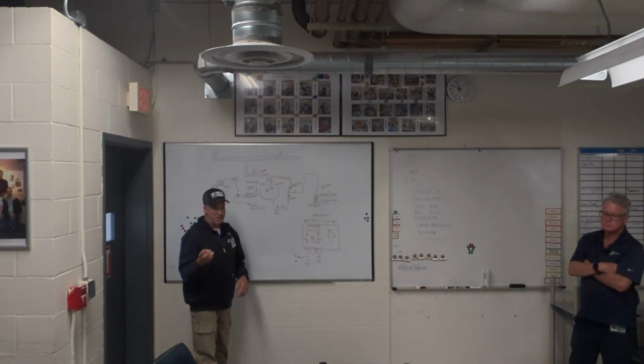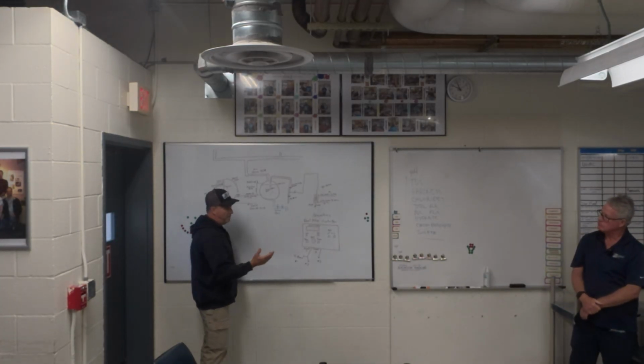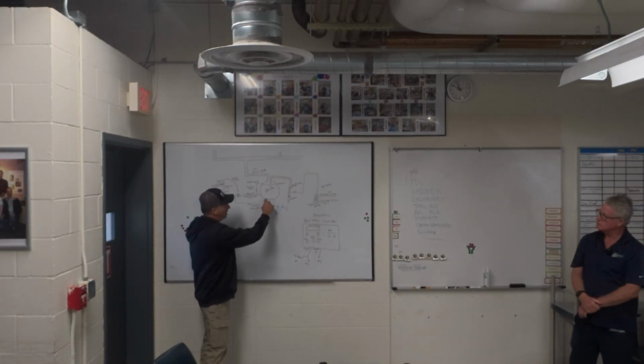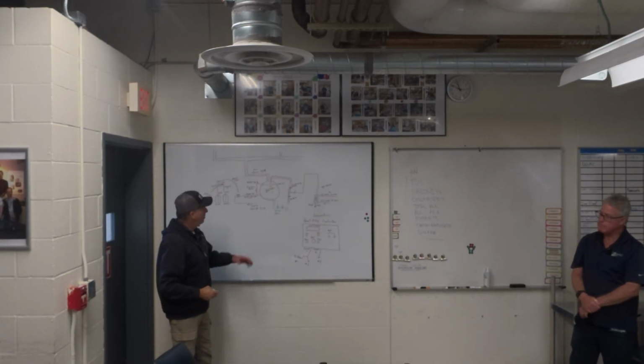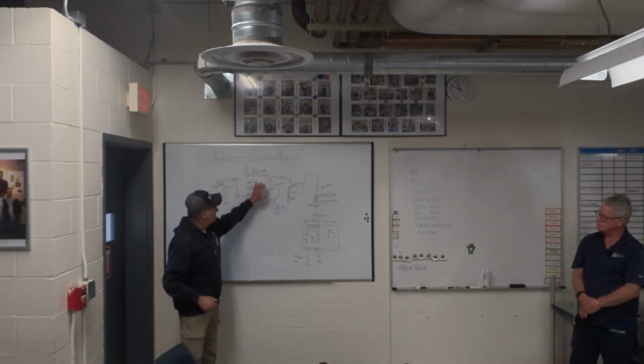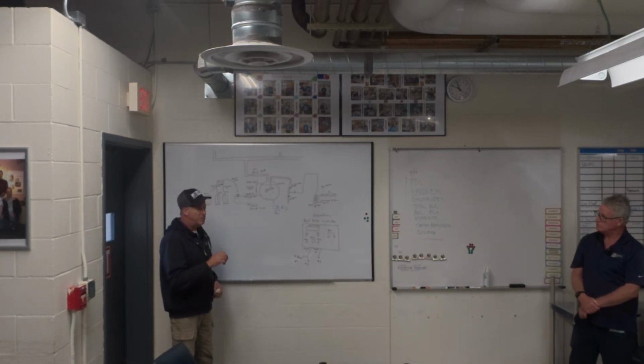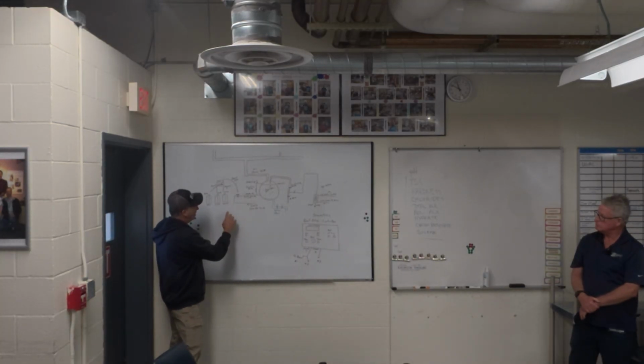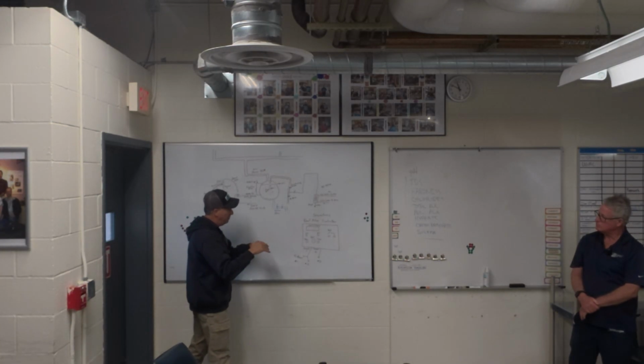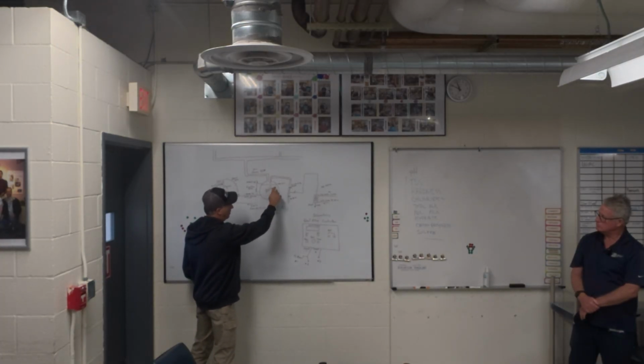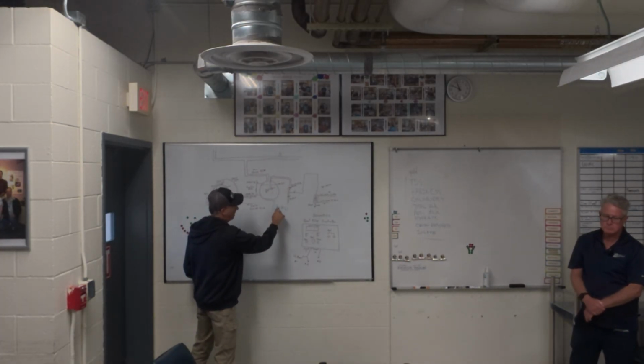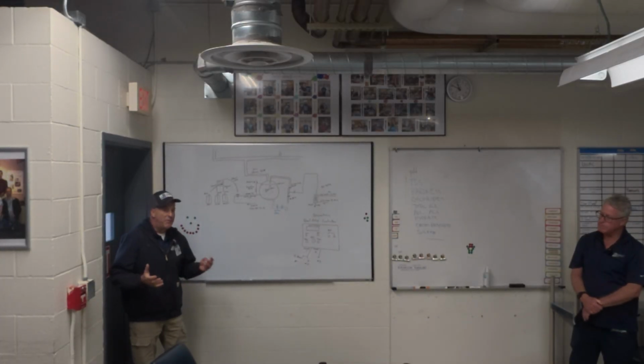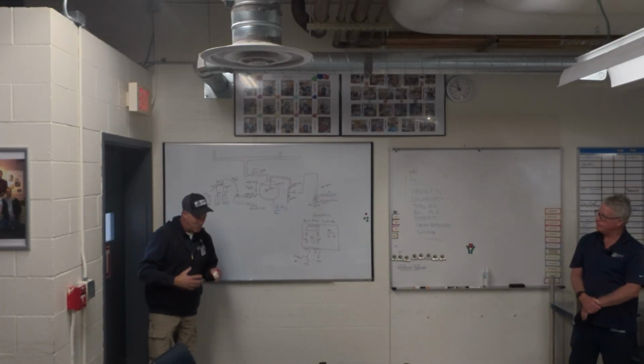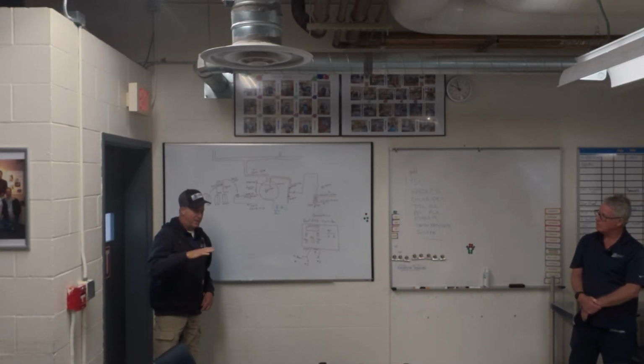But still, it's incumbent upon the operators, with the advice of the consultants, to periodically blow the reactants out. Some people don't really get this, but these are two different ways to fine tune the chemistry within the boiler proper. Not only are we fine tuning it with our injection pump and our controller for chemical additives, but on the back side, we're fine tuning it with our automated blowdown and manual bottom blow. So you have two different ways of looking at what's coming in and what's going out, and we can really tune those. Over time, the trend gets really smooth, chemical usage is down, energy usage is down.